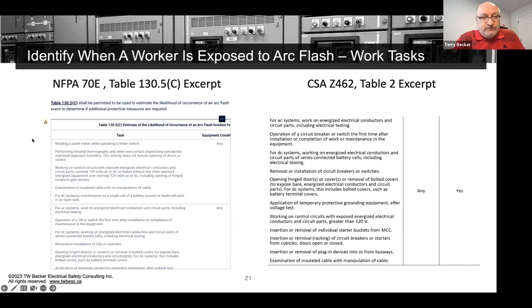All right, so great tools. If you're not aware of them, take a look at them. This is really where this needs to start, right? Work task-based electrical hazard identification, and then electrical hazard classification against, again, the different electrical equipment, the different voltages that we have workers performing energized electrical work on. So you're going to go, well, Terry, we don't do energized work. Our policy is we don't work live. And I hear that often. I go, wait a minute. Are any of your workers doing any of these work tasks? Because if they are, and they're using one of these, right, then they're doing energized electrical work, right? So testing for absence of voltage is actually energized electrical work with an approved test instrument as well. So great resources. Again, great toolboxes, these two standards.